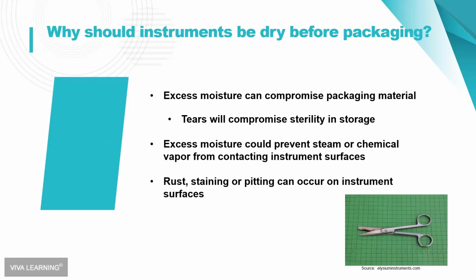So although I wasn't planning on focusing on the cleaning cycle for instrument processing tonight, I just want to mention something, because I said earlier that we need to dry instruments prior to packaging. And there's a couple of reasons for that. One is that if you put wet instruments into a pouch or wet instruments into some kind of a sterilization wrap, it makes them prone to tearing. And if they tear, then you compromise the sterility of the packaging, the instruments, when it goes into storage.